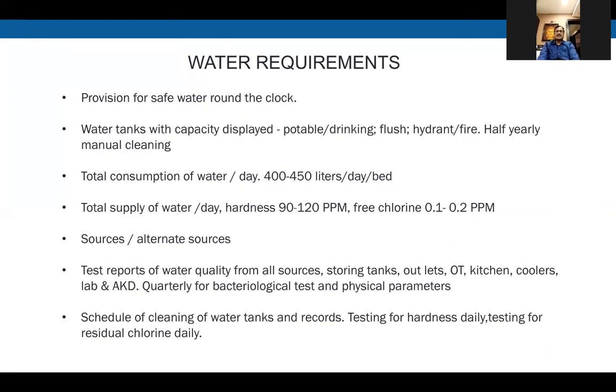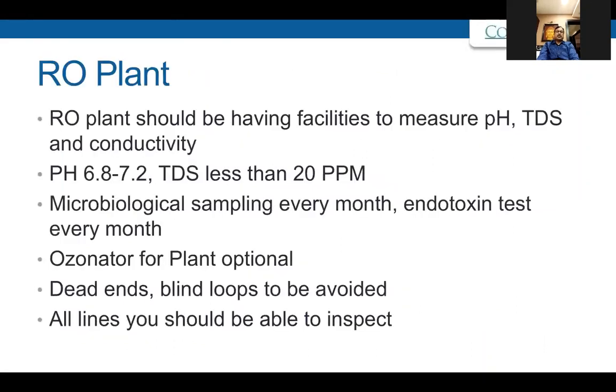So testing for hardness daily, testing for residual chlorine daily. This task must be understood. Another very important installation is the RO plant. In the RO plant, I have seen that normally people don't check the pH, which is a very important aspect. In many of the hospitals, even the dialysis technicians are not very much aware that pH has to be checked on a daily basis, and there is a need to correct this pH, because if it is acidotic, then again patients face problems. If it is towards the alkaline side, again patients will face problems. So TDS, conductivity, and pH are compulsory in RO water.